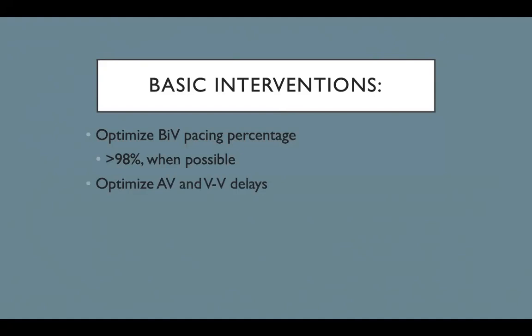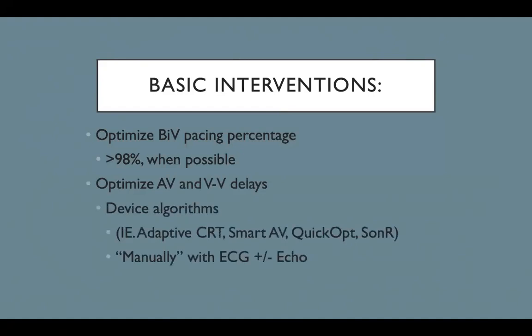So remember the diagram of the activation sequence. We're trying to achieve within each individual the optimal timing of electrical activation to achieve the mechanical resynchronization. So we can do that most often today. It's done with device algorithms such as the adaptive CRT algorithm from Medtronic, Smart AV from Boston Scientific, QuickOpt from Abbott, and the SonR system from Sorin.